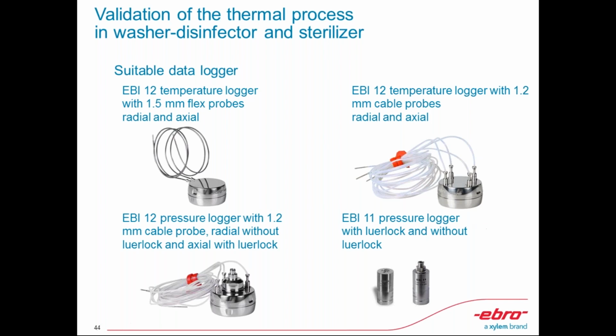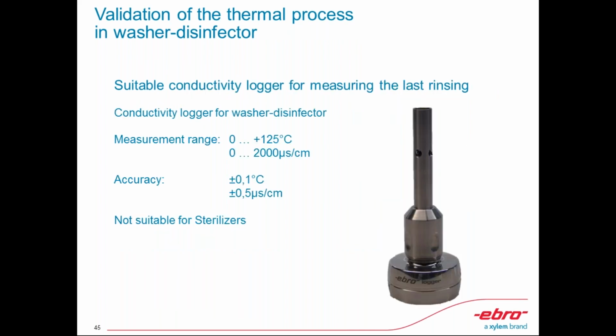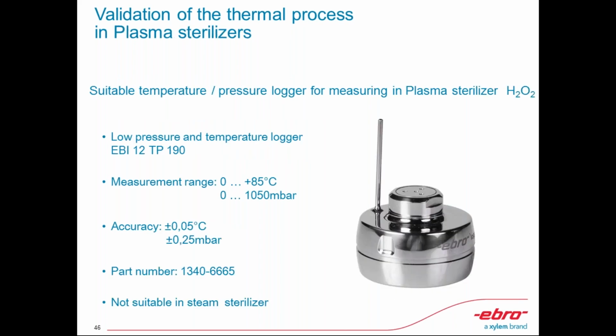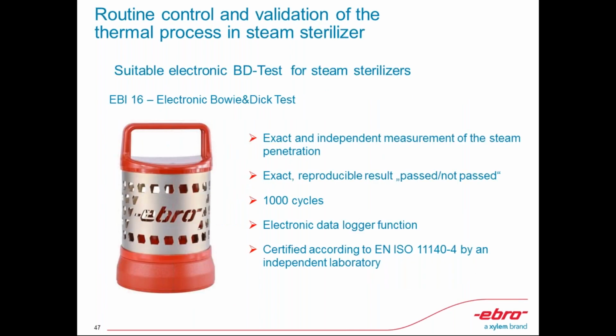And we also have, as an option, the mini loggers, the EBI11, the conductivity logger, which is very important for washer disinfection processes. It is a good trend that we started with Ebro, and I think it is being copied now by some of the competition, but we are faring very well. We have the pressure sensors with temperature sensors and the Bowie and Dick test logger. So this is a good alternative for your chemical indicators for your Bowie and Dick procedures for autoclaves.